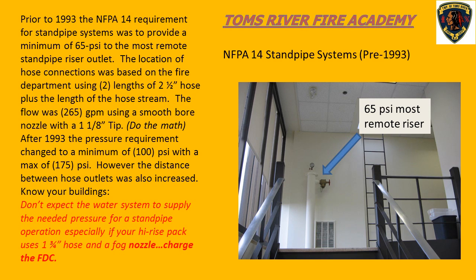New systems after 1993, the requirement is 100 psi at the most remote riser. But if you're dealing with a standpipe system, don't rely on the street pressure for the standpipe. Go ahead, hook up to the standpipe system, get your pressure 150 to 200 psi into the system for the hose line that's going to be operating off the standpipe.